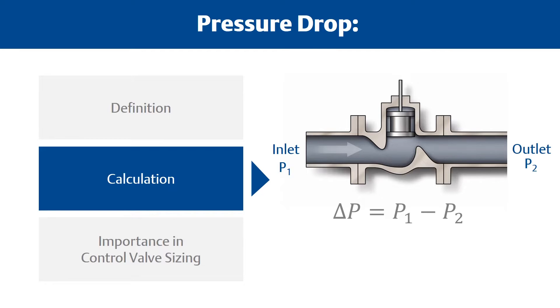Inlet or upstream pressure is shown as P1. Outlet or downstream pressure is shown as P2. P1 is measured two pipe diameters upstream of the valve. P2 is measured six pipe diameters downstream of the valve. Your process or instrumentation department will provide these variables.